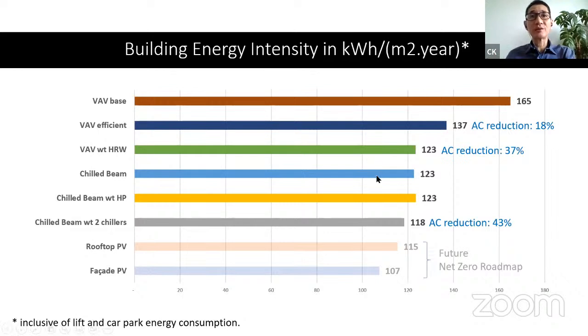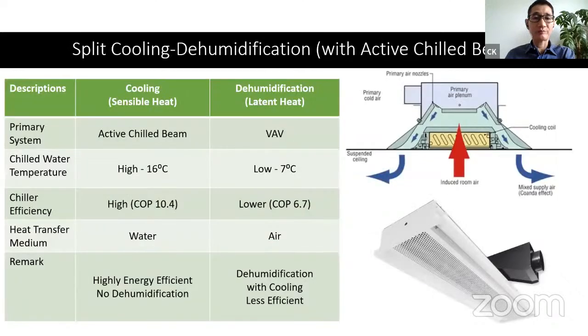The client wanted us to explore chilled beams. So we looked into chilled beams, but designing them using the conventional method does not reduce much of the energy consumption, even with adding the heat pipe in there. But once we take advantage of the chilled beam feature where it can operate at high temperatures, we see a major reduction. We are talking about at least a 43% reduction in energy consumption from the base case scenario. Future implementation of rooftop PV and facade PV will drive this building closer to a net zero scenario.